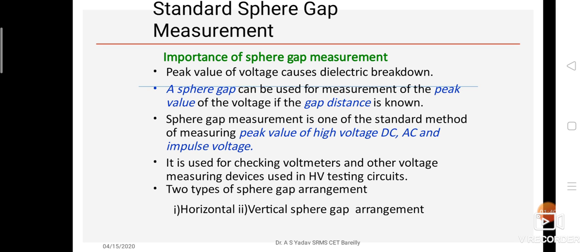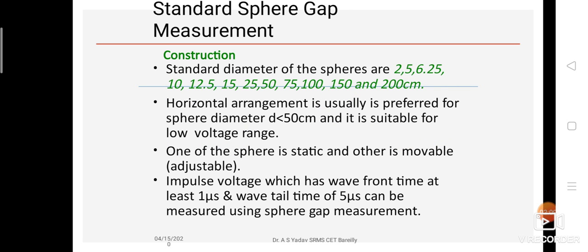Generally, two types of sphere gap arrangement are used, horizontal and vertical. These spheres are made of metal such as copper, aluminum or brass, of identical diameter, with their shank, operation gear and insulator support as shown in the figure. Next slide. The voltage to be measured is applied between the two spheres, and the spacing between them gives a measure of the spark voltage. A series resistance is usually connected between the source and the sphere gap to limit the breakdown current and to suppress the unwanted oscillation in the source.